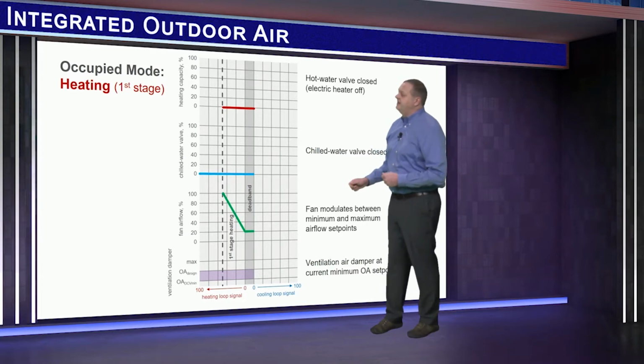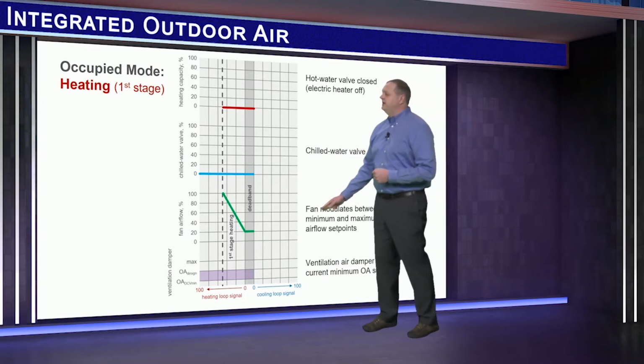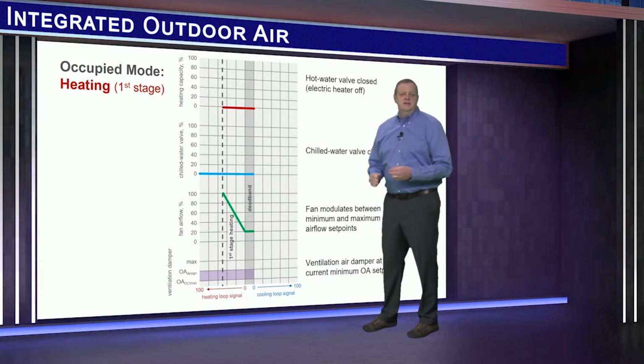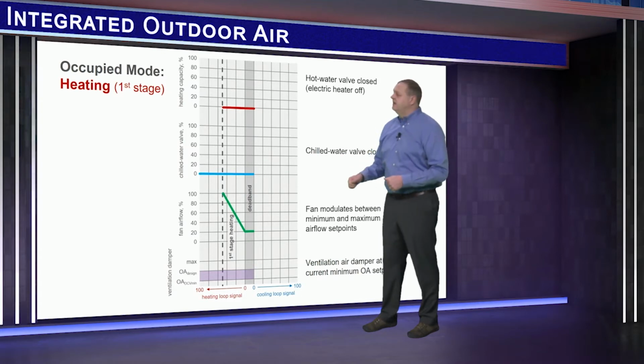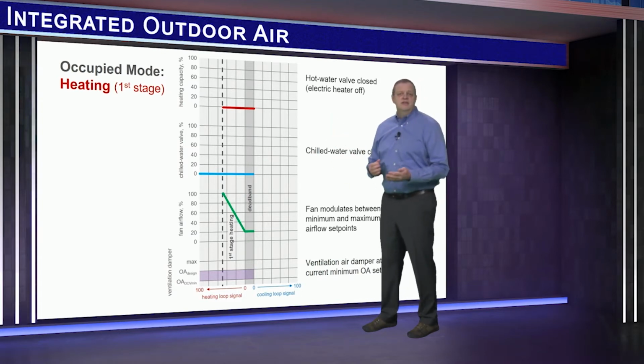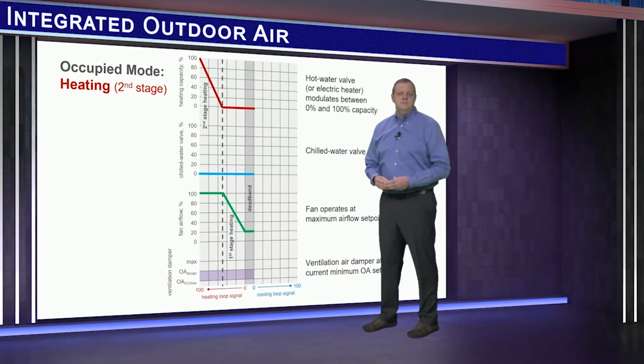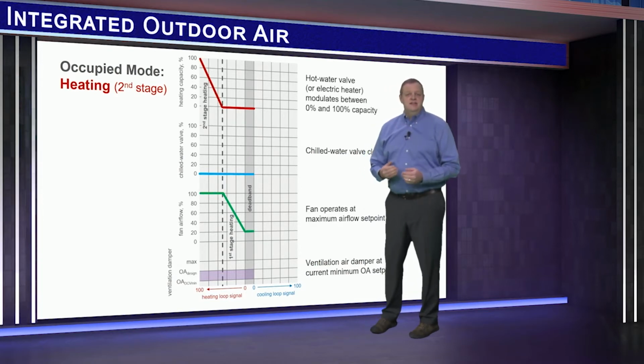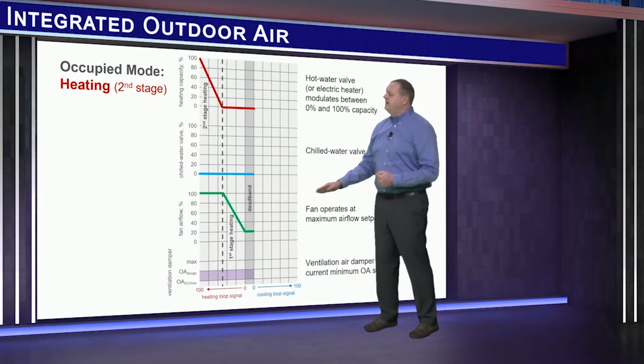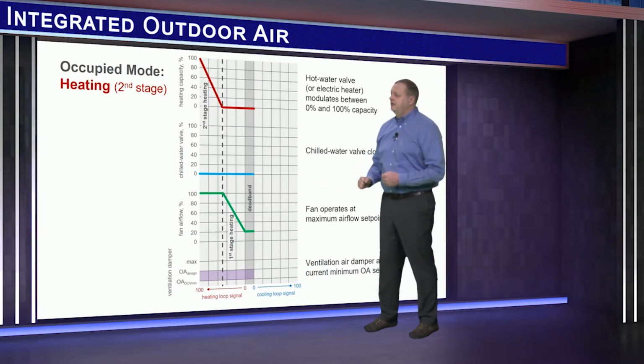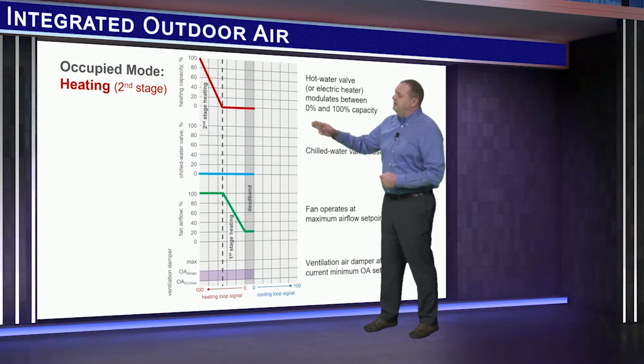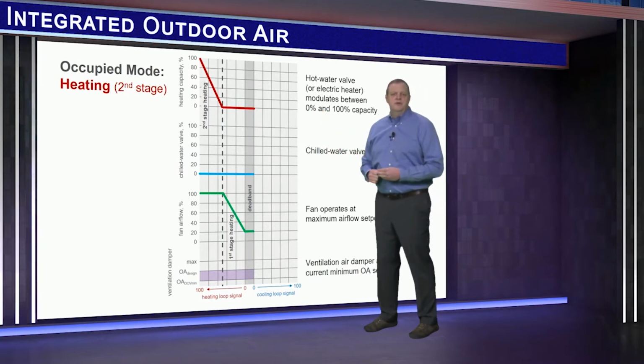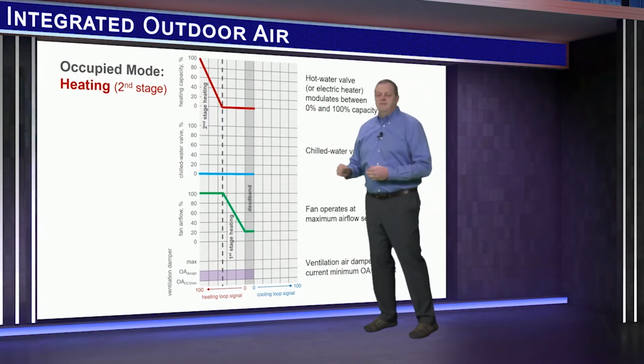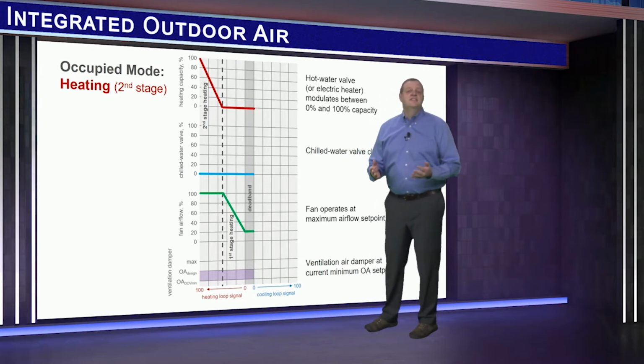Moving from this dead band to the left, the controller first begins to increase the fan speed. This recirculates warm air from the ceiling plenum to maintain zone temperature. In this first stage of heating, the hot water valve or electric heater remains off. When the requested heating capacity is increased to the point where the fan has reached its maximum airflow set point, the controller then begins to modulate the hot water valve further open, while the fan remains at maximum airflow. This is the second stage of heating.